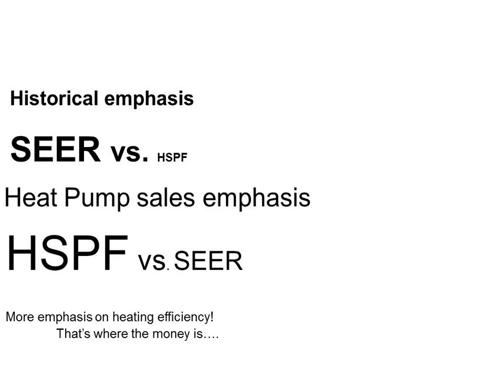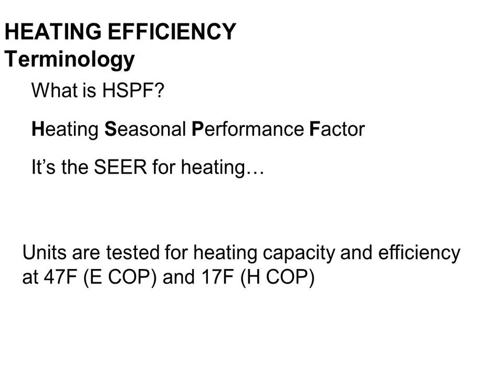In our climate, where it's cold, SEER is irrelevant, and I'll show you financially on some calculations here in a little bit that the cooling efficiency of a small system, residential like commercial, doesn't matter at all. There's so few cooling hours relative to heating, it doesn't make a difference. The heating efficiency is where all the action's at. Now, if you're doing a downtown high-rise with a bunch of core zones and year-round cooling, okay, fine, the math is different. But for small commercial and certainly for residential, heating efficiency is most important. So when talking about a heat pump, HSPF is more interesting and exciting to us than the SEER rating.